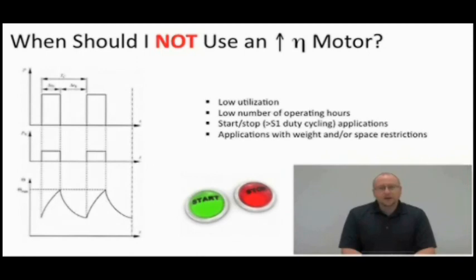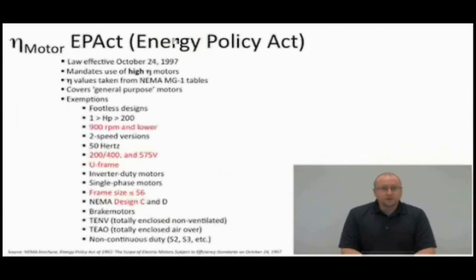And just to briefly touch on some of the laws that we have here in the United States concerning energy efficient motors. There's a law called EPAct. It's the Energy Policy Act, and that went into effect in 1997. It was written back in 1992, and that law basically says that all motors that we use in industry need to be high efficiency or greater, and those high efficiency values are determined from NEMA MG1 tables. They took those values and used them in the law. But there are many exemptions to this law, and some of the exemptions make a lot of sense. The concept of it is, when you're cycling a lot, like a brake motor, a brake motor is going to be cycling because it has a brake to cycle. If it's not a continuously rated duty motor, like if it's not an S1 motor, you're not going to be running it enough to gain the energy back.